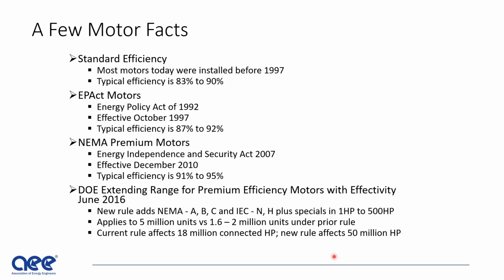Typical efficiency is 83 to 90%. The Energy Policy Act of 1992 tried to improve energy efficiency on motors because of the large load, as we saw earlier. Typical efficiency is 87 to 92%. Then in 2007, with the Energy Independence and Security Act, the hurdle was raised again to NEMA premium motors, which are typically 91 to 95% efficient, depending on their size. The larger the motor, the more efficient.